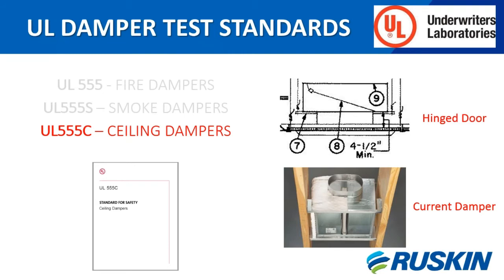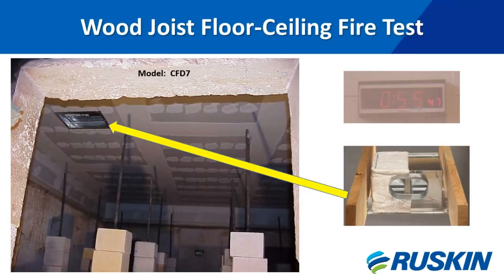Ceiling dampers are used in specific fire resistance design alternatives. Some floor-ceiling or roof-ceiling design specifications include one or more ceiling radiation dampers covered by this method of evaluation, and are generally tested along with the design constructed in accordance with the standards for fire tests of building construction and materials. For the UL 555C fire test, the damper is installed in a current UL fire resistance floor-ceiling or roof-ceiling assembly. The actual installation method is determined by the manufacturer of the damper.